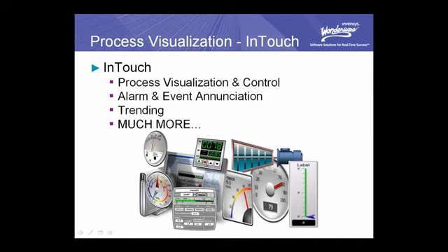Probably the most significant difference is what these graphics actually contain. Not only are they visual elements drawn and animated, but these graphics also contain their own data point definitions and scripts. So they behave like mini applications, and you no longer need to mix animation enhancing scripts with your supervisory logic or even with the window logic of your HMI. These graphics contain their own scripts as well as their own data points. This enables us to create really good looking graphics that are generic enough to be used in virtually any application. So a meter that is used in one app can easily be reused in another, and the creation of these custom points doesn't require additional licensing or tags.